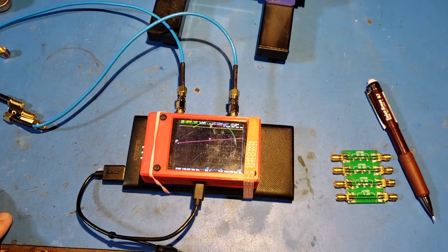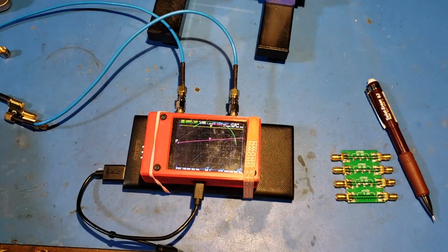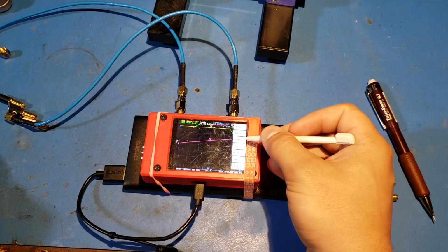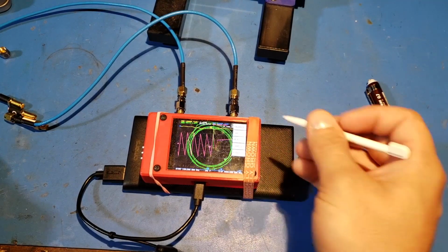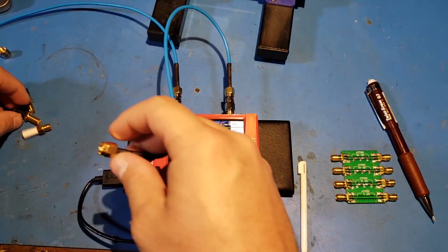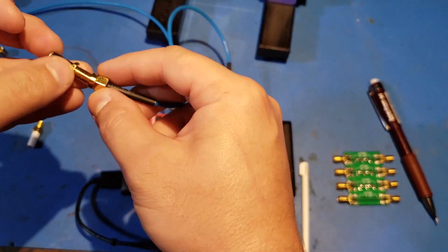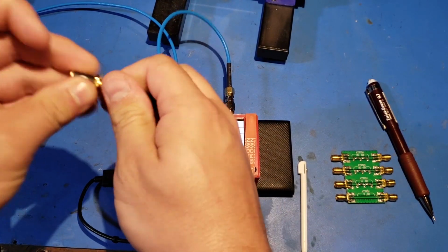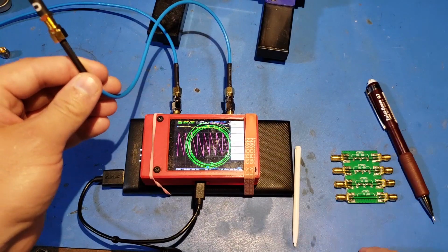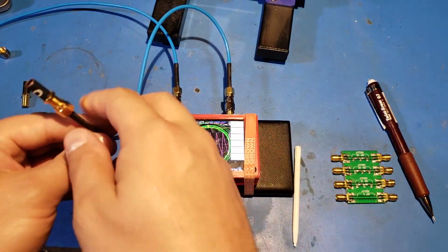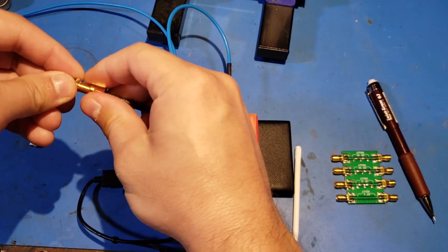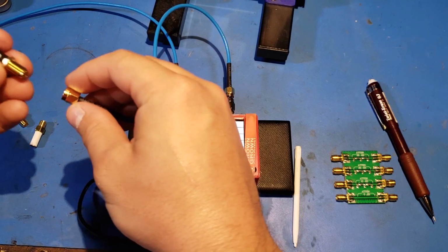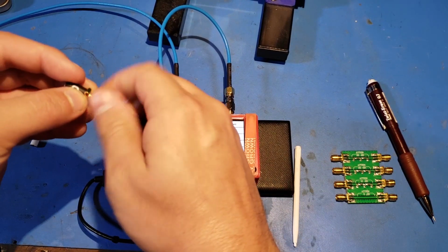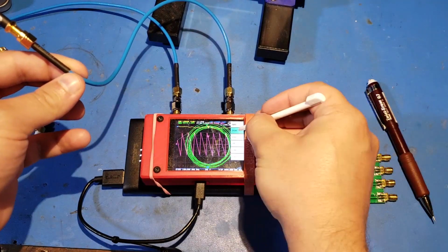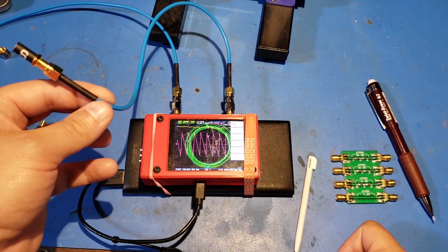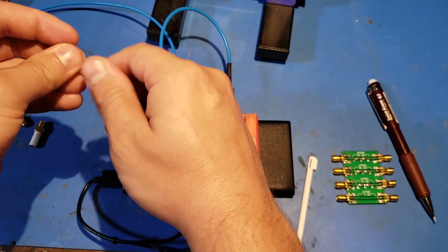For the third calibration, we'll be doing a one-port calibration on the female SMA standards. So first we'll go into the cal menu, we'll hit reset a couple times, and then we'll hit calibrate, and we'll start connecting our standards. First we start with the open, which has an O on it for open. Once that's done, we'll disconnect that and connect our short. Then we'll disconnect that and we'll connect our load.